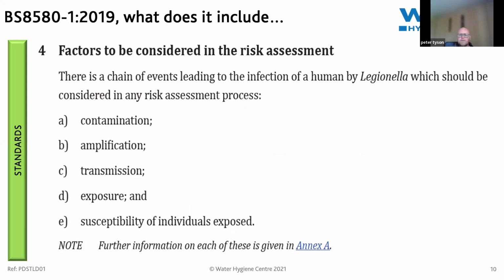Contamination: Legionella is a naturally occurring organism. It's ubiquitous, appearing to be everywhere. It's found in rivers, lakes, reservoirs, ponds, streams. It can be in your mains water system at low concentrations, because they don't have to provide us with sterile water. It's wholesome, potable drinking water that they need to provide us with. And as we know, Legionella bacteria can be drunk until we're blue in the face. It only becomes an issue when it becomes an aerosol and is inhaled into the lungs. Those aerosols have got to be small, 5 micron or less, to be inhaled into the deepest, darkest tissues of your lungs.